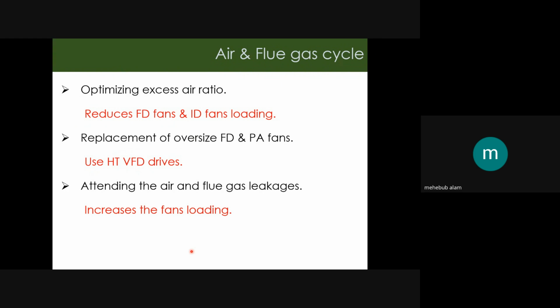In air and flue gas systems, as told, we have to optimize the excess air ratio, reduce the forced draft fan and induced draft fan loading, and replace oversized forced draft fan and PA fan by using a variable frequency drive, because VFD has a very good opportunity to reduce energy consumption in the power industry. For that, we have to do a proper study of whether the drive size is more than the requirement, and that is done through an energy audit. Also attend to air and flue gas leakage. If there is any leakage in the air and flue gas path, it will increase the fan loading. Fan loading means ultimately it will increase the power consumption.